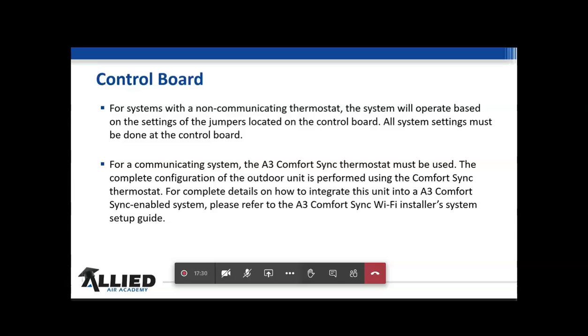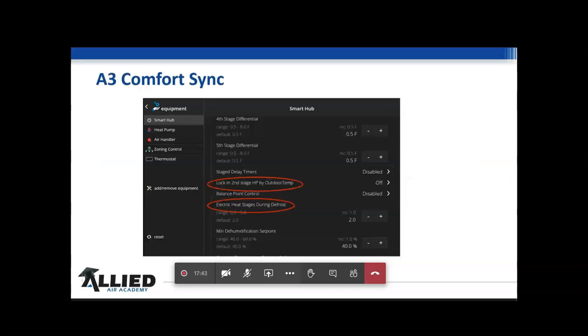So let's talk about the A3 and when we're doing our setup, because I made this mistake until I went back and looked at it while I was doing this, and went, oh man, I've clean forgot. I was supposed to go back in and look. So I went into equipment, my smart hub. Again, I'm not going to go through how to get to this. We've already gone through the A3 and done that. So there's a couple of things here I want to talk about. Lock-in second stage heat pump by outdoor temperature and electric heat stages during defrost.